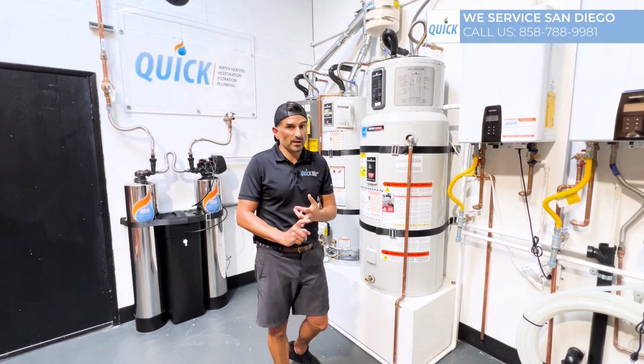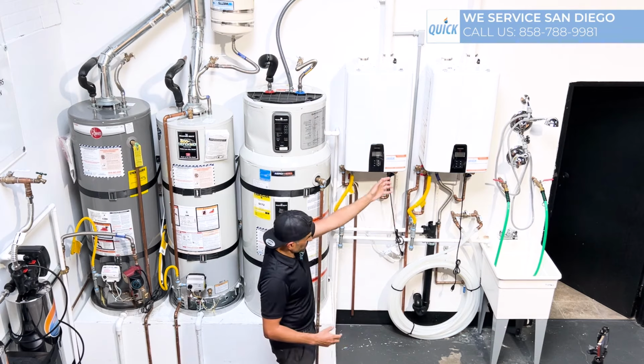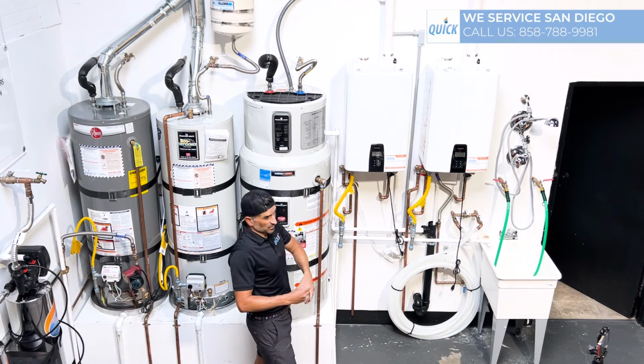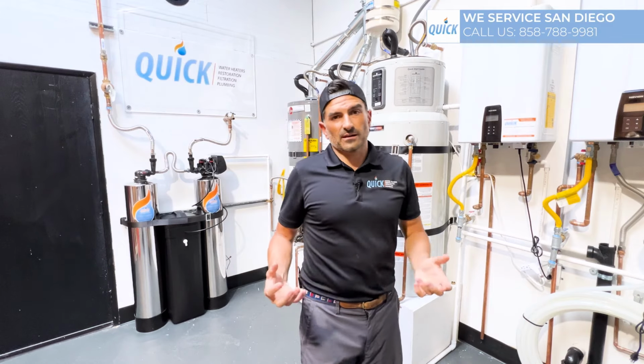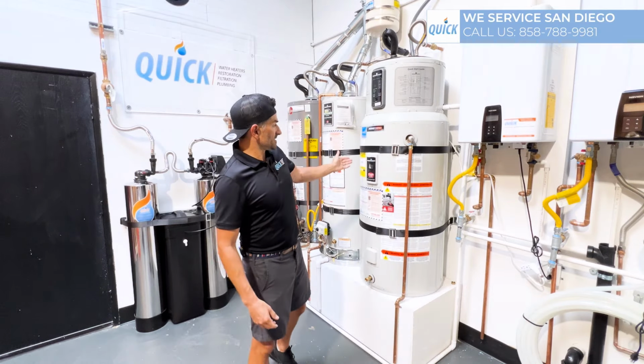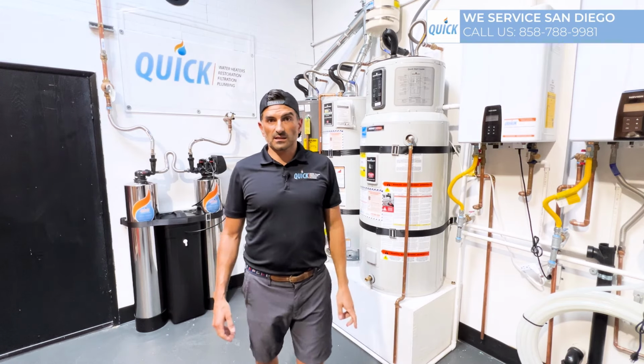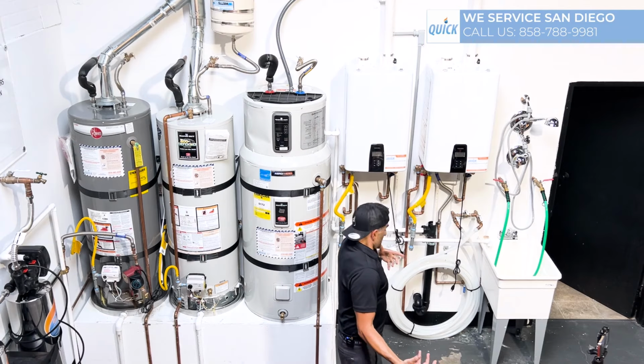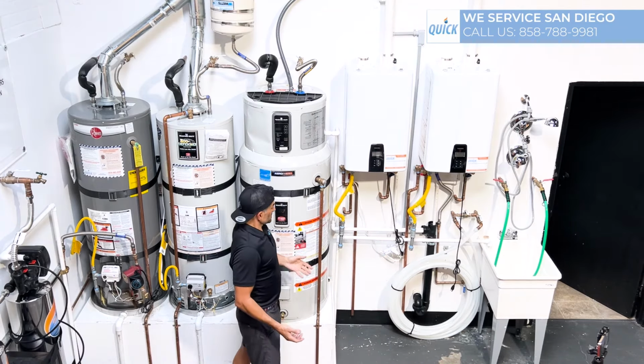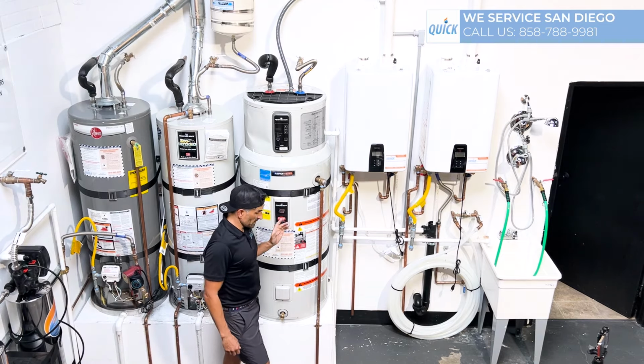It's not something you really want to do unless you're a single person or you have a small family or you understand that you're just not going to have a lot of hot water. You're going to need to change all the flow restrictors on your faucets to make sure you don't use too much hot water. But if you're game with all that stuff, they are kind of cool, honestly. We set this up in our shop to test it out. It does work. It runs all night before it's hot again the next day. If this were in my house, I would probably be pissed. But I want to let you know what's going on with the water heaters so that you can make an informed decision. In California, I don't really recommend them.